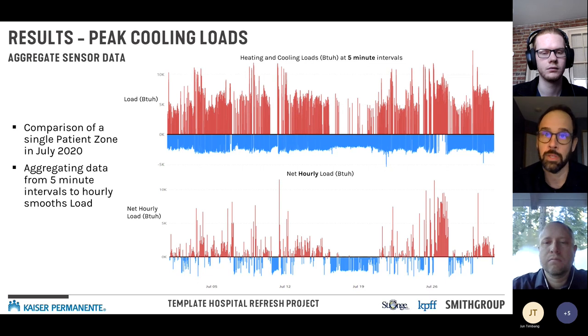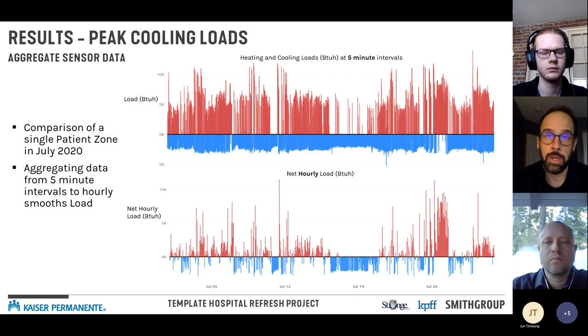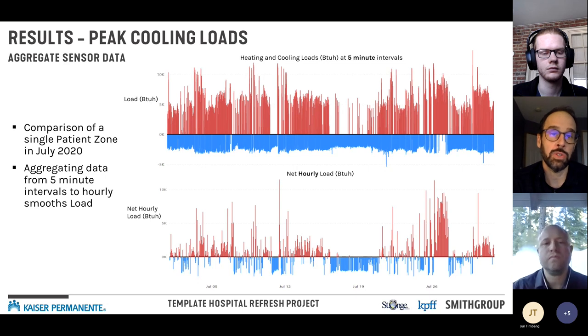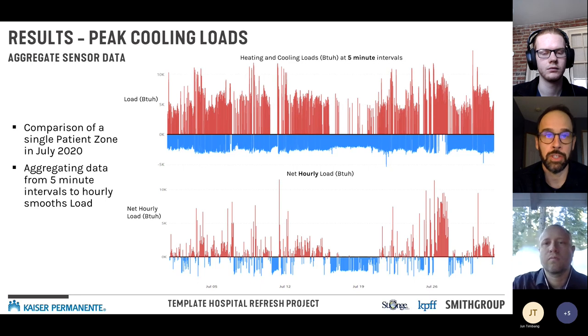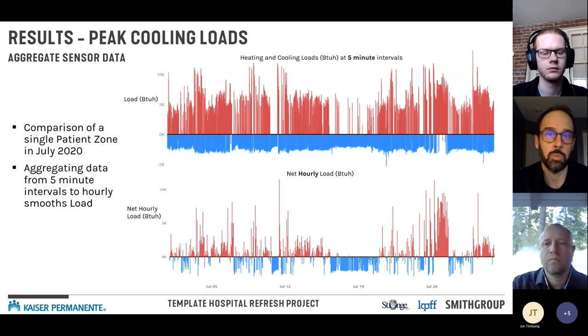Even in July, this patient zone showed a lot of heating occurring. To deal with this, we aggregated up to an hourly net load in BTU/h on the bottom graph — same data, same zone, but averaged across each hour. This produced what you'd more expect: distinct heating and cooling periods. This approach made more sense for the data and was used for the rest of the analysis.